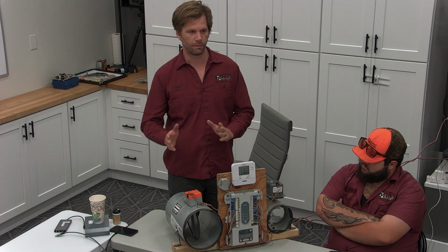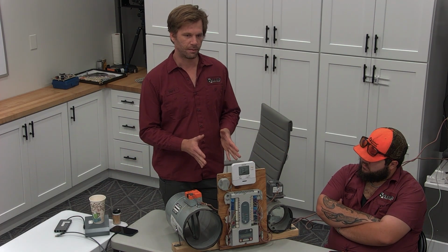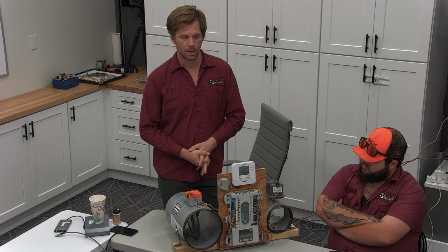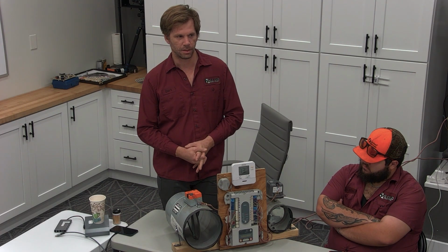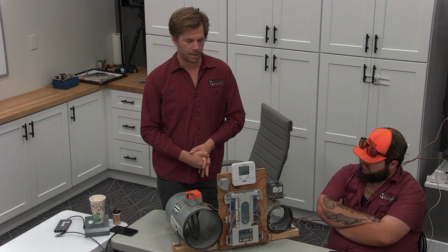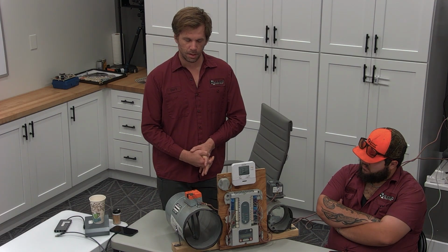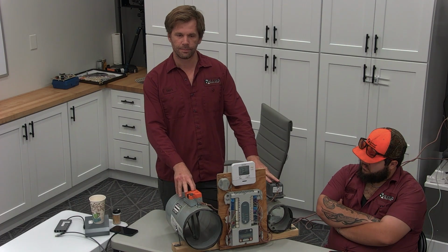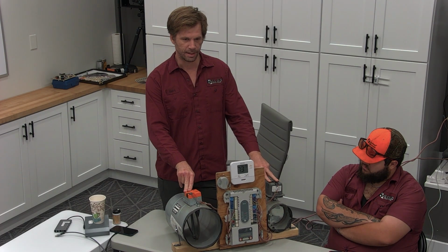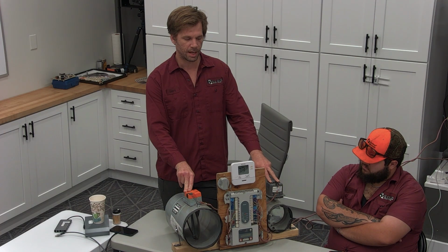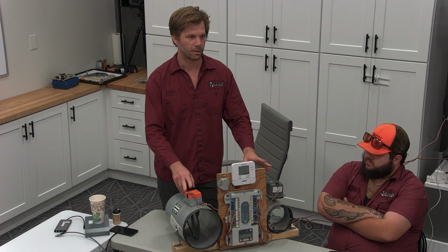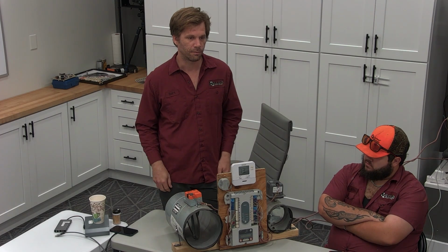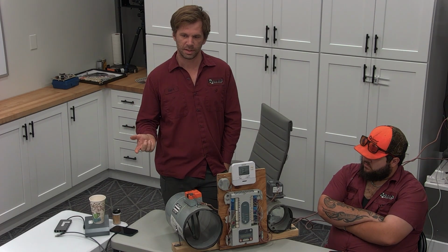If you cross all of those boxes off and you come back and you still have an issue, that's when you can start looking at the board. Another thing with the damper systems that we need to all remember is that the best way to diagnose issues with airflow, with the damper motors and their controls, is in the house, not in the attic, right? So in the house we have our damper board, our thermostats, and our vents for airflow. And so turning on the thermostats, confirming if there's airflow, turning off one of the zones at a time, and seeing if that zone closes and airflow stops with your hand.